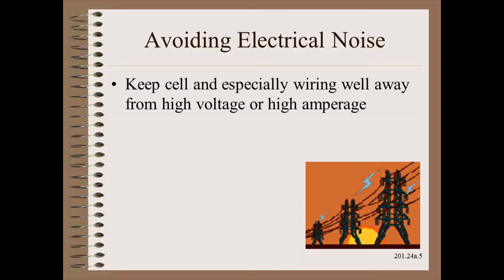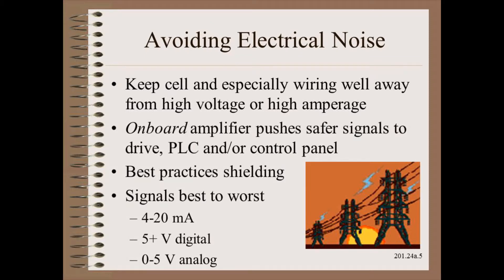Electrical noise is ever present in our plants and is one of the bigger risks for load cell problems. We don't want that noise to ever talk to our load cells. We start with good design practices that avoid the problem in the first place by keeping the cell and especially wiring well away from high voltage or high amperage wiring such as motors, static bars, corona treaters, and other devices. The next step would be to use onboard amplifiers that push more robust signals through this risky space. The signals from best to worst include 4 to 20 milliamps, which is nearly bulletproof; digital signals, which are usually okay; and 0 to 5 volt analog signals, which are getting risky. Millivolt signals from remote amplifiers are, in my mind, never mill duty or safe enough to run any distance.